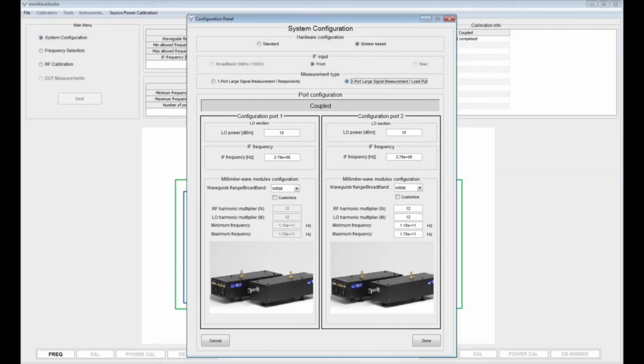And finally, we need to configure our frequency extenders. In the port configuration section, we can specify whether we are using the same frequency extenders on both the input and the output by clicking coupled. This will ensure that the settings applied to port 1 will be automatically propagated to port 2. In the port configuration section, we need to specify the local oscillator power that needs to be injected into the frequency extenders, the desired intermediate frequency, waveguide flange, in this case we are using WR6 frequency extenders, and then we can customize the RF and LO harmonic multiplication factor, and minimum and maximum operating frequencies. When we have finished configuring the system, we click Done.